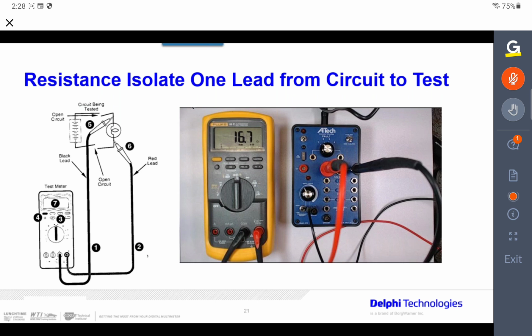I had a guy at a class I was doing recently - he had 5 mega ohms on a circuit. Well, the reason he had 5 mega ohms on a circuit is because the computer was still in that circuit. You always want to pull one leg out. We're doing voltage testing in parallel, we're doing ohms testing in parallel, we always do current in series. It makes a big difference.